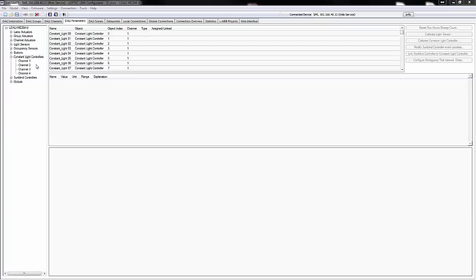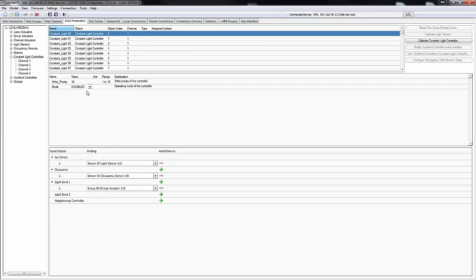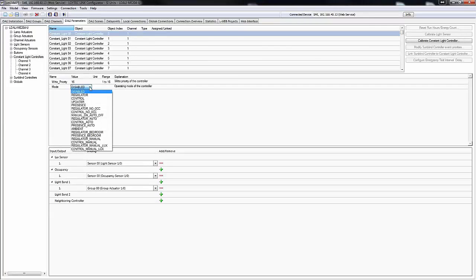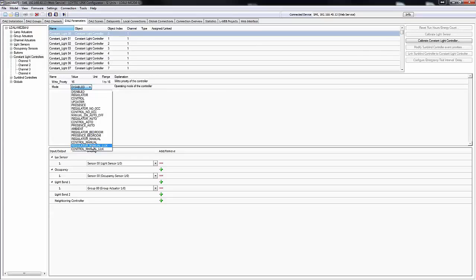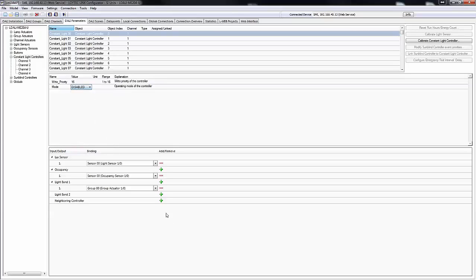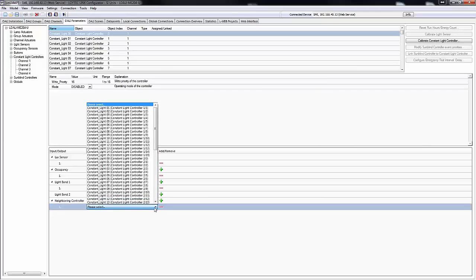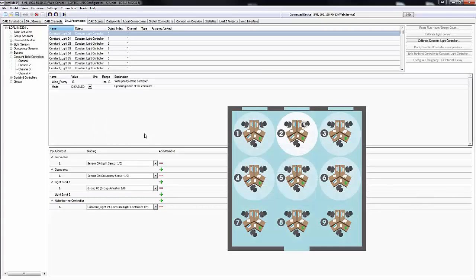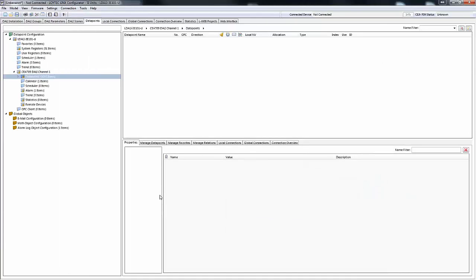The ConstantLightController application was extended. The modes Control and Regulator have each received a new variation. In both variations, the automatic mode must be manually activated. The automatic mode will be disabled whenever lights are switched off, either due to becoming unoccupied or due to enough natural light being available. The new neighboring controller function has been developed specially for use in open office spaces to provide a more pleasant atmosphere and reduce contrasts to unoccupied areas.